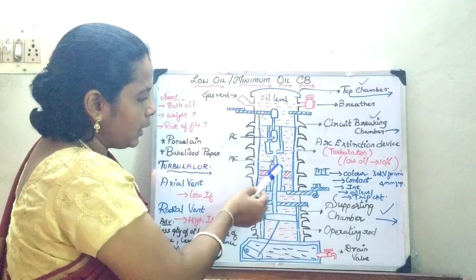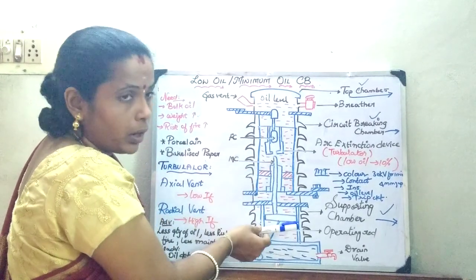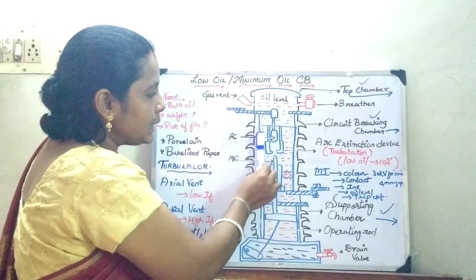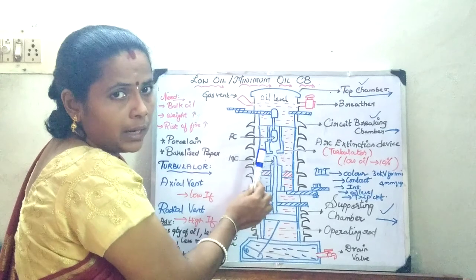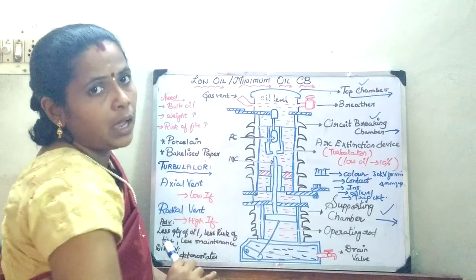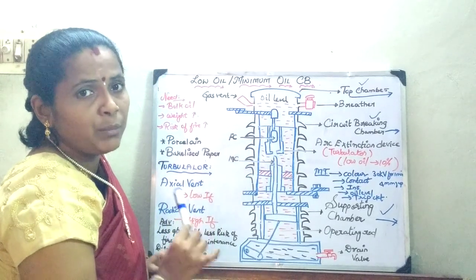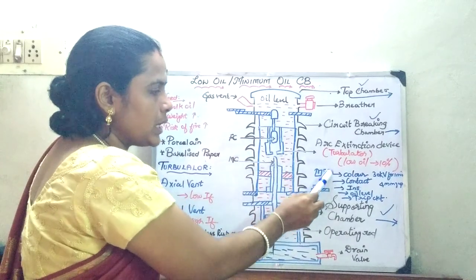So the principle is that whenever a fault occurs, through this piston, this moving contact is going to be moved apart. And this turbulator is acting as an arc extinction device through your radial and axial vents, it quenches the arc. But the main limitation is its maintenance process.